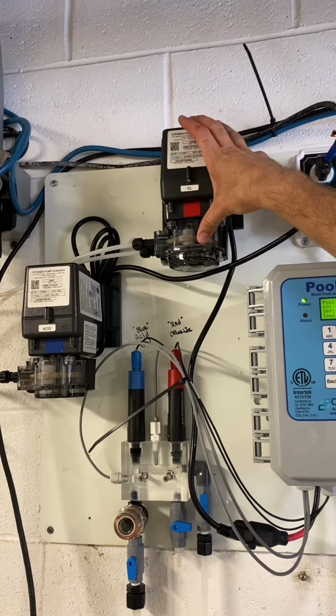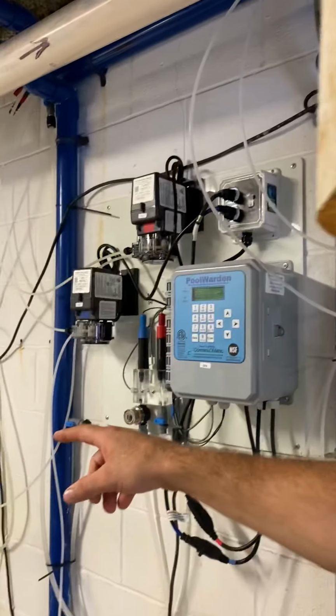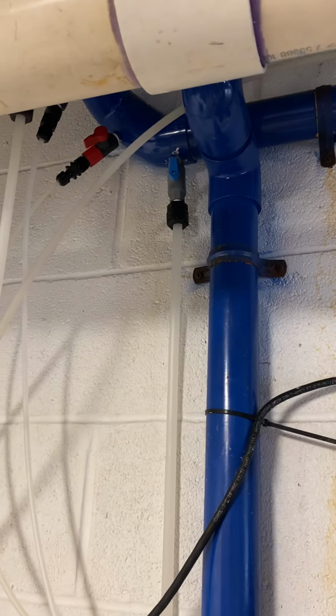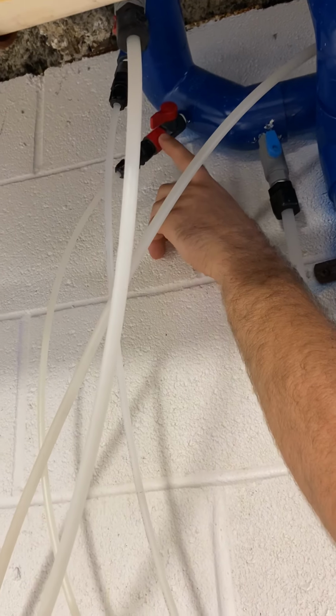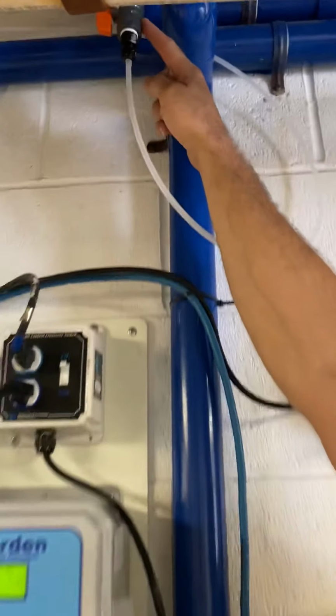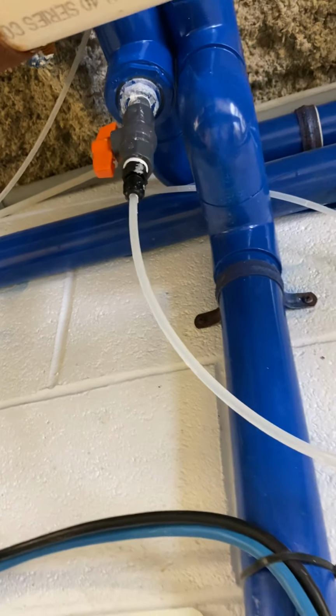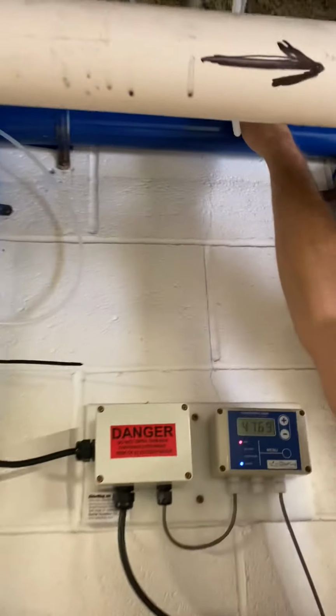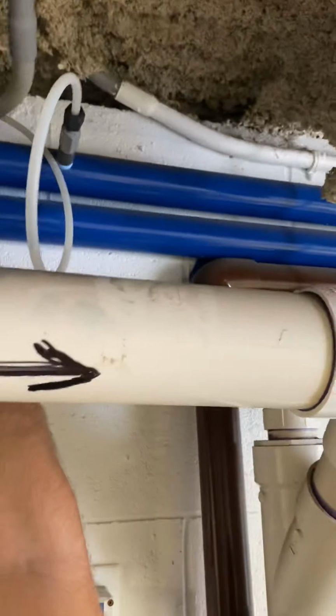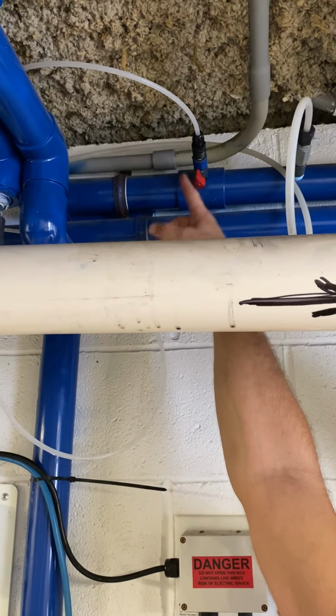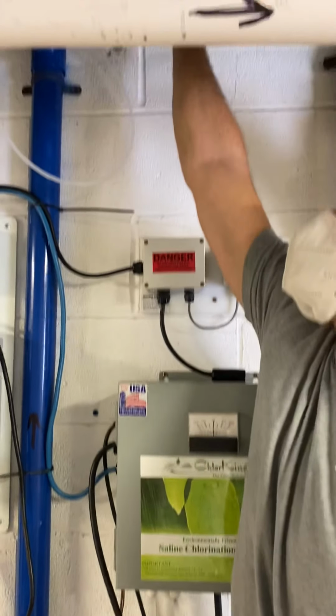You have this chlorine pump as well as your spa chlorine pump both pulling liquid chlorine from this 150-gallon double wall container. It pulls liquid chlorine out of that, goes through the system, and it goes through these 1/4-inch tubes, which gets injected up to here. Okay, everything's labeled, so if you recall, the red probe is for your chlorine. I taped this up here, so this is where your chlorine gets injected. One over here, and one over here, which I will have taped red as well. When you're doing the pH, if you're using CO2, that's what your CO2 injector is. And if you're using acid, this is your acid injector. Remember, blue probe is for acid. I taped it blue as well.